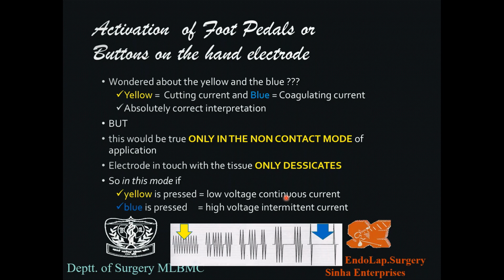That's why I said it is only in the non-contact mode of application. I'll just show you what this basically means. So this is basically what happens when you're just pressing the yellow pedal. This is what happens when you're pressing the blue pedal. Because when the electrode is touching the body, either through your artery forceps or otherwise, you're only desiccating. You're not cutting or coagulating. You're using a cutting current, using a coagulating current, but you're not cutting, you're not coagulating. Remember that. That is very, very important to understand, right? So yellow pressed, low voltage continuous; blue pressed, high voltage intermittent current.